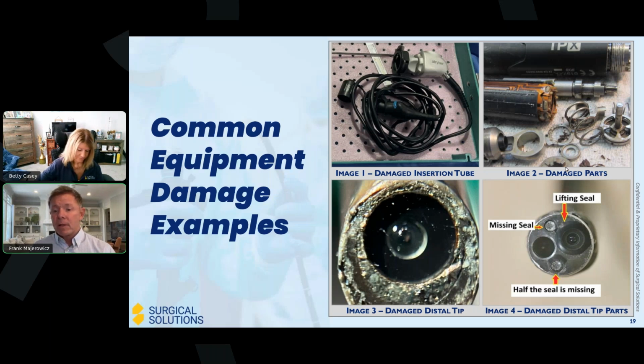And then you can see what this slide is really trying to point out are the seals that are missing. Those lenses at the tip of the endoscope are sealed with an adhesive type sealant. It's not to hold the lens in, but it's to prevent debris from building up around the edges of those lenses. And they are also there to help prevent reflection during the procedure, to stop reflection from getting into the glass and into the image components of the scope there and the lights. So it all kind of ties together. But here you can clearly see that those seals are missing or peeling apart.